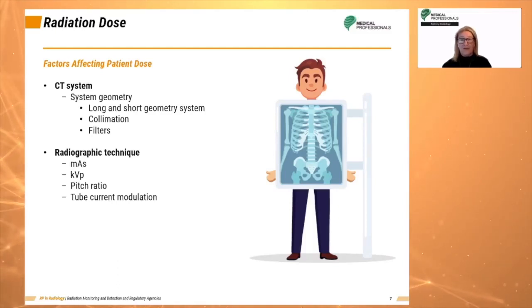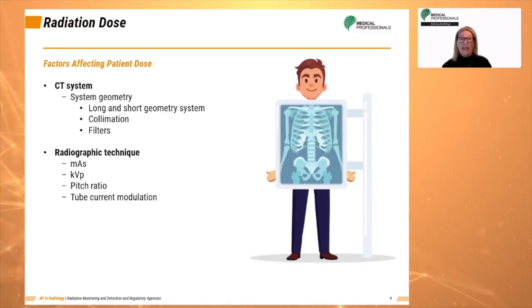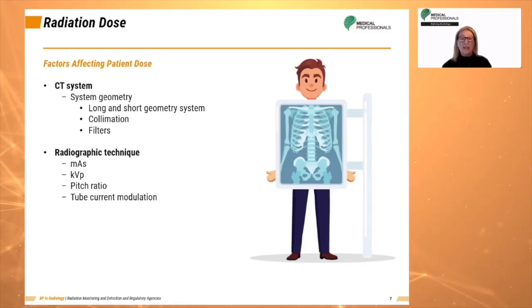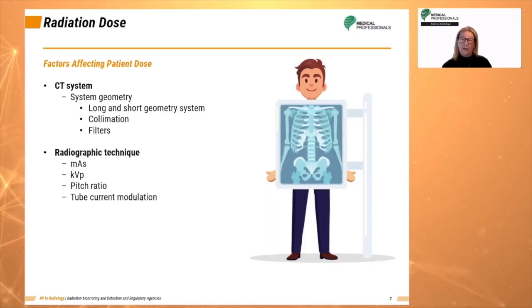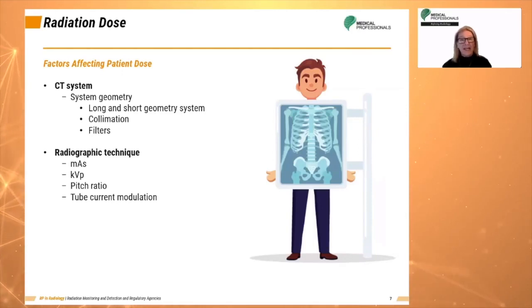Among technologist-controlled factors, the applied MAS value is defined by the product of exposure time and x-ray tube current. It determines the quantity of photons reaching the detectors. Increasing MAS improves image quality by reducing noise but increases the patient dose, just as in conventional radiography.